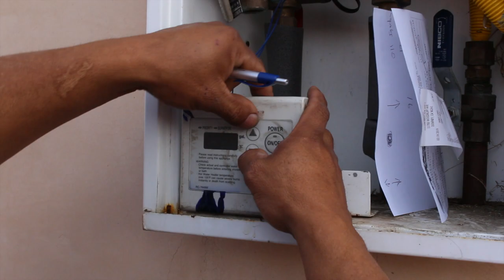Okay, error code 16. Code 16 is a sharp spike in water temperature outlet. Scale buildup, which hampers heat transfer. Okay, so it needs a descale, most likely. That's what I'm going to recommend to the customer.